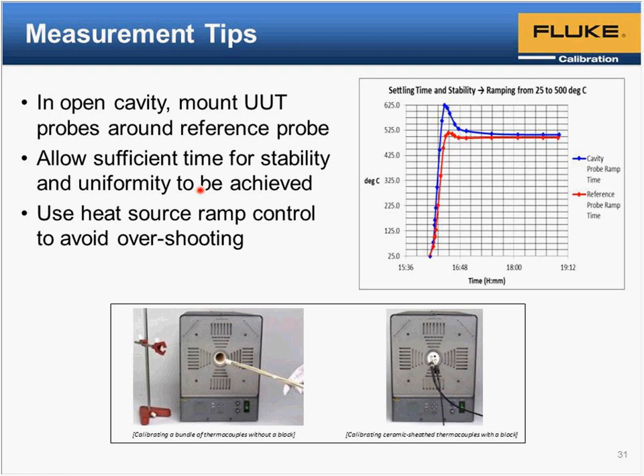We have this picture because it shows two different configurations for calibrating thermocouples. The one on the left is an open cavity method, where you bundle the thermocouples together, and typically in this situation the reference probe is in the center and the UUT probes are added to the reference probe in a bundle. The one on the right is where an equilibration block is used, and we'll look in a moment at what the differences are.